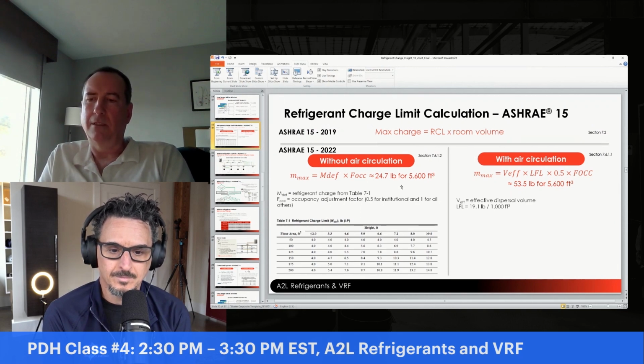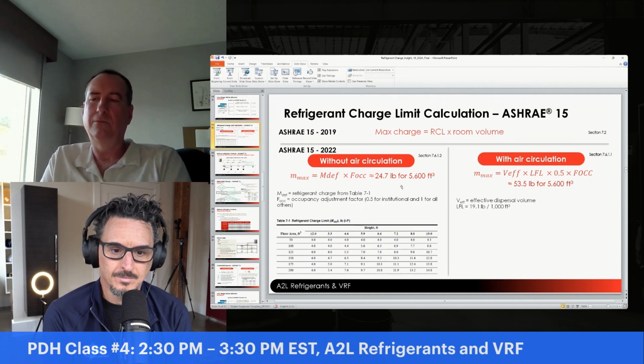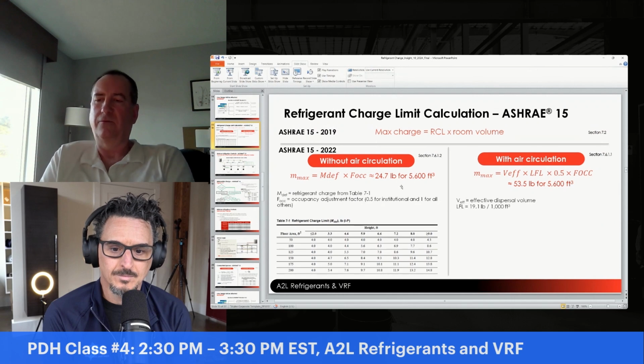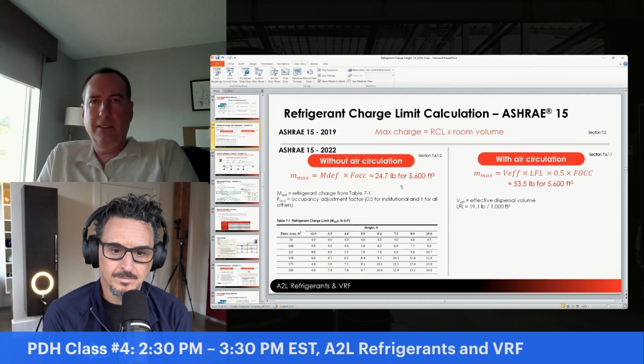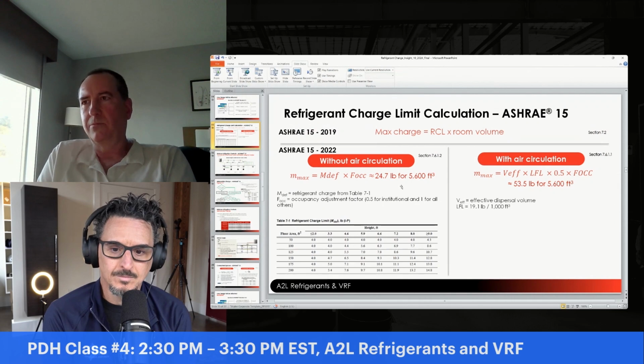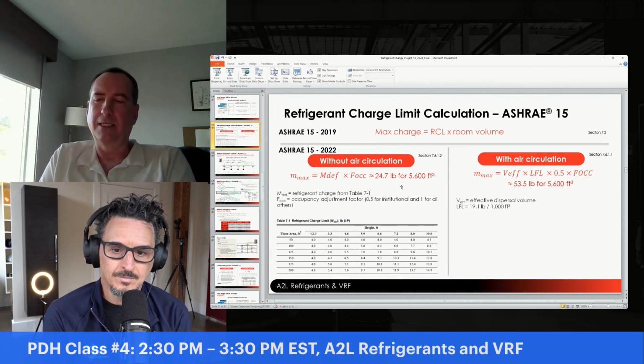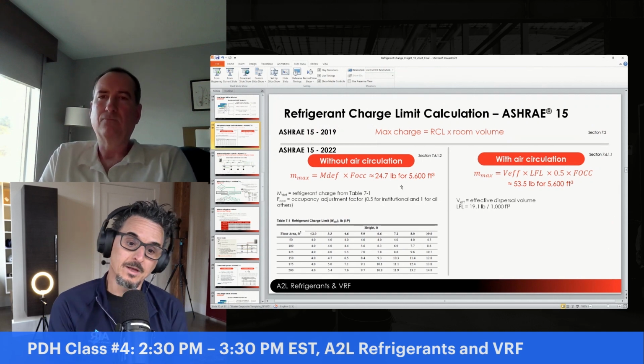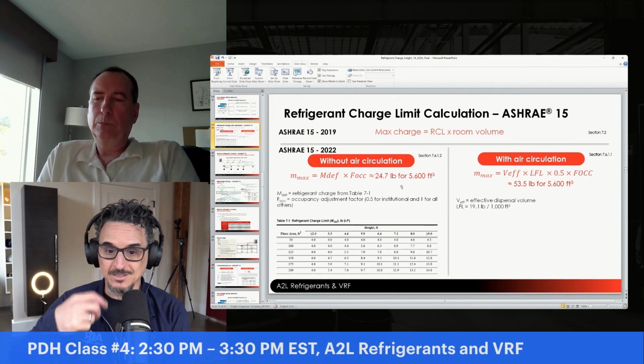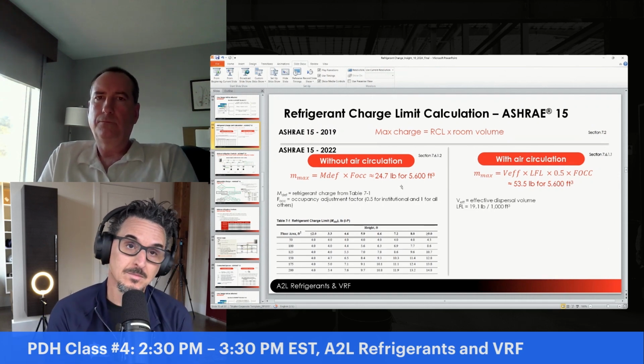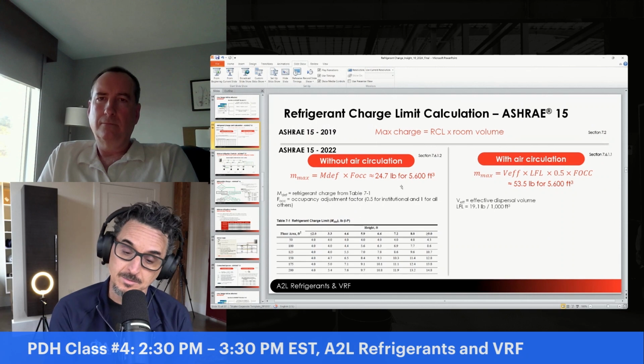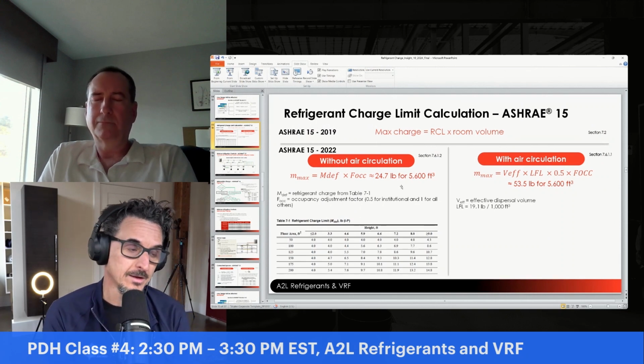And so in this example here, 24 and a half pounds of refrigerant is allowed for a space with 5,600 cubic feet of volume. So that would be a 700 square foot room with an 8-foot ceiling. So 25 pounds. And for comparison, one of our 2-ton split systems with like 90 feet of pipe and a couple of cassettes is about 8 pounds of refrigerant. So the max is way over that. Right. And the max the system can have that would potentially leak into that space. Correct. Am I saying that correctly?